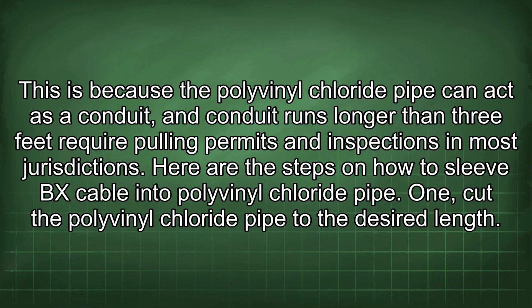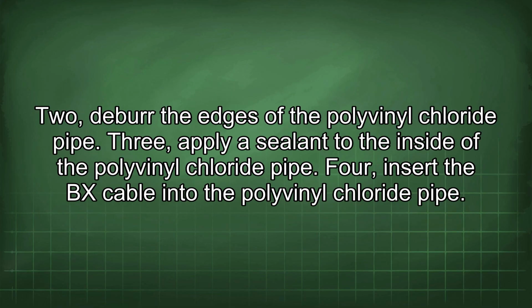Here are the steps on how to sleeve BX cable into polyvinyl chloride pipe. 1. Cut the polyvinyl chloride pipe to the desired length. 2. Deburr the edges of the polyvinyl chloride pipe. 3. Apply a sealant to the inside of the polyvinyl chloride pipe. 4. Insert the BX cable into the polyvinyl chloride pipe.